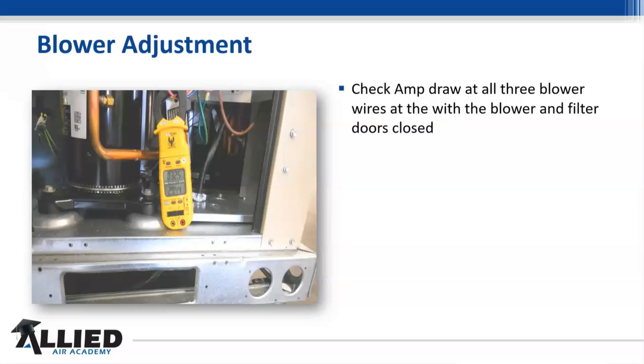This is extremely critical, especially when we get into the VFD drives in just a moment. It's going to be really important that we check this, and that's where our balance sheets that we worked on last week, and I showed you the examples, that's where this is going to come into play as well too, especially when I start getting into the VFD drives and the percentages that it's going to have to be within to work. It really gets critical at that point.